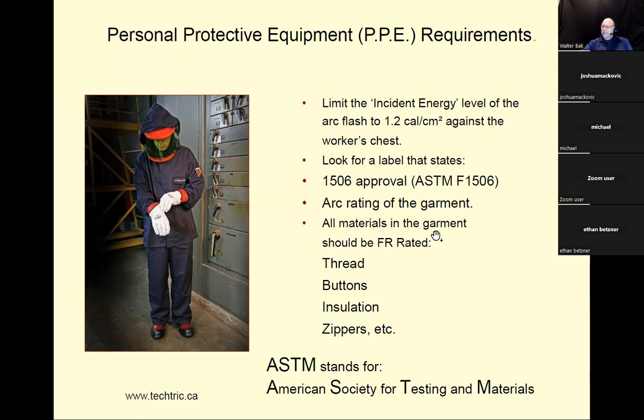All materials in the garment should be flame retardant rated. Okay, so here's the thing, that should be a topic. And then there's the explanation: all materials in the garment should be flame retardant. Not just the fabric, but everything on it that can catch fire. If the buttons can catch on fire, you are on fire and you're going to feel that burning on you. So we have to make sure that all the materials used to produce that clothing are flame retardant. That includes the thread, the buttons, insulation, zippers, and whatnot.